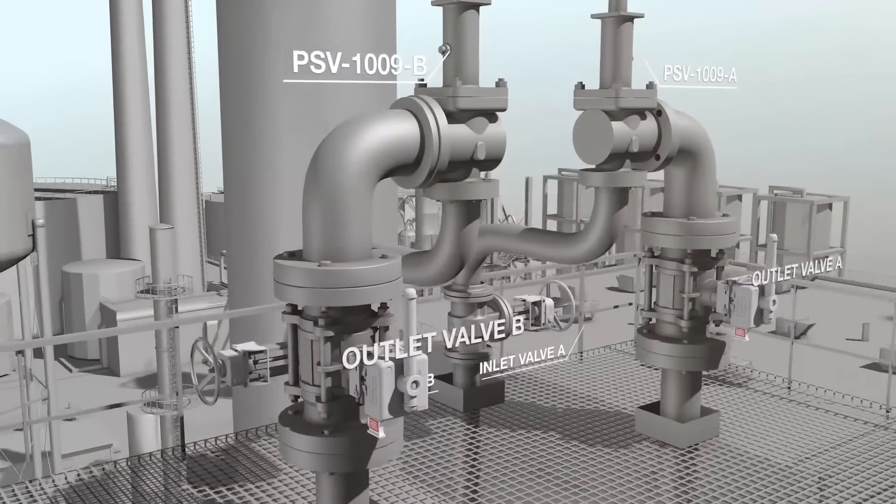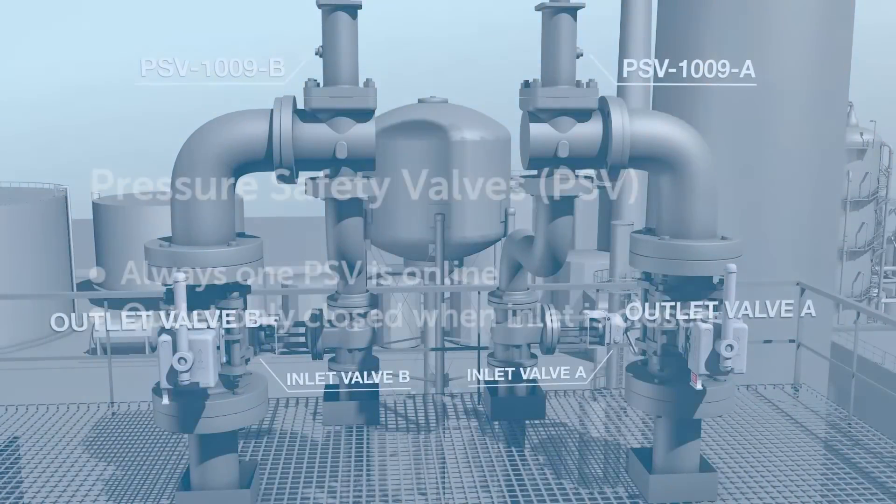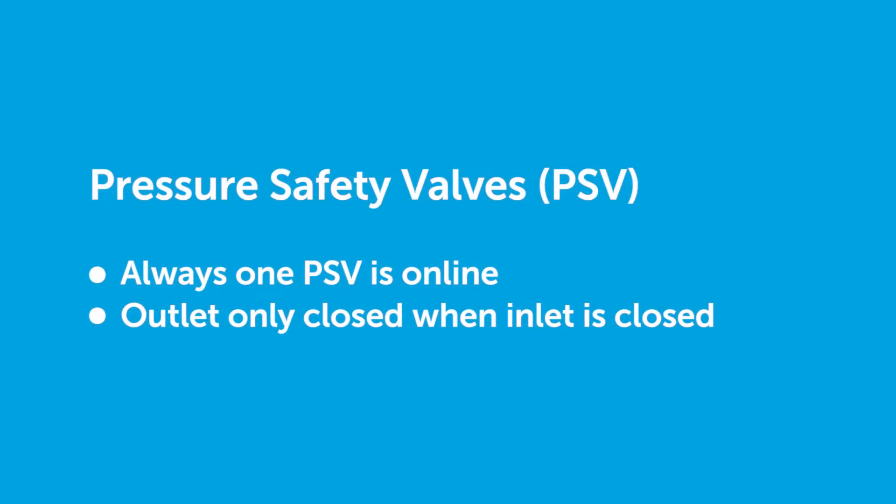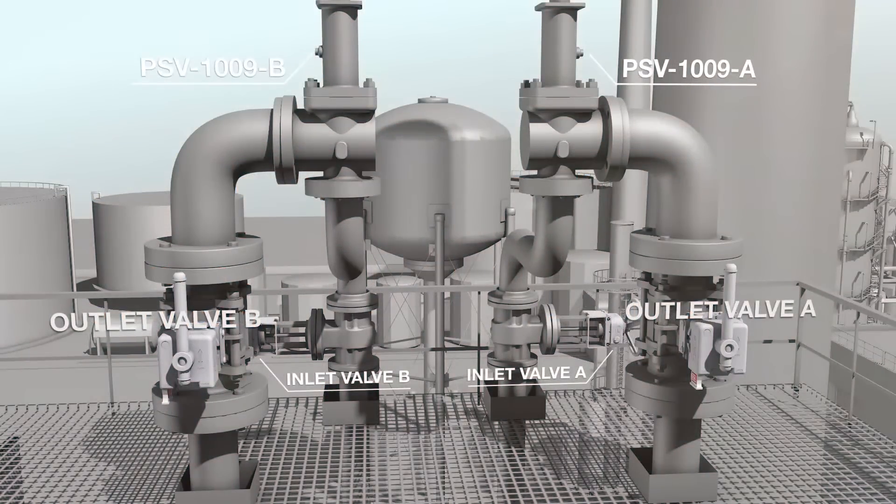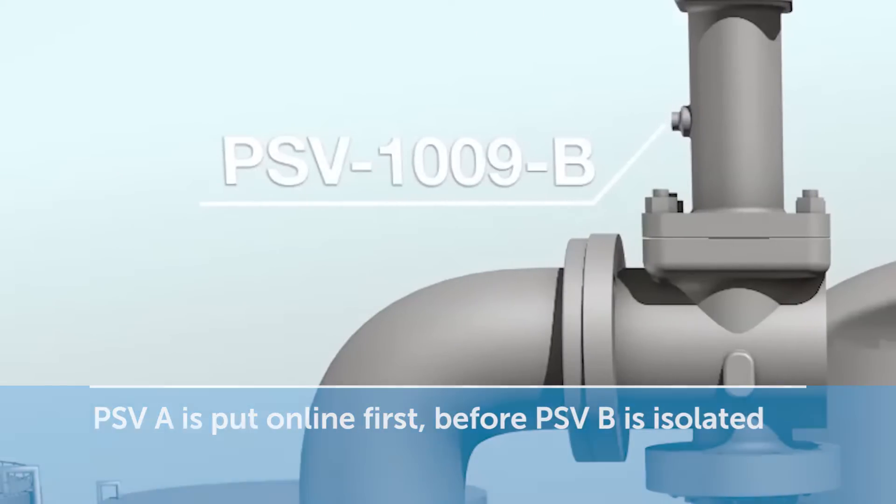In a parallel PSV system, inlet and outlet valves are interlocked to ensure that at least one relief valve is online at all times. In this example, PSV A is put online first before PSV B is isolated.